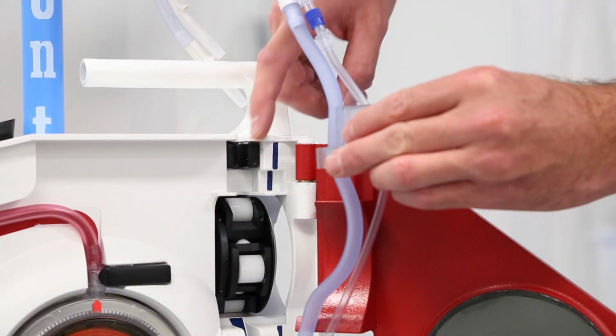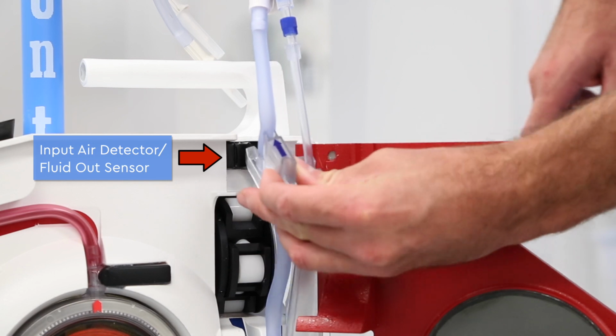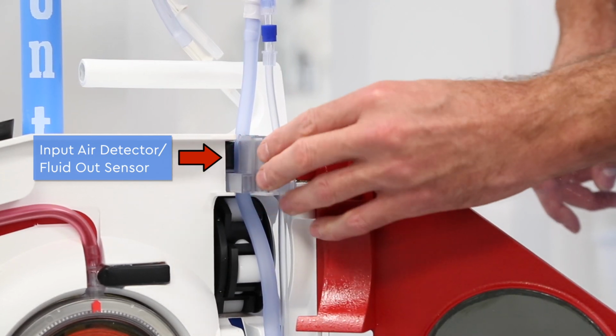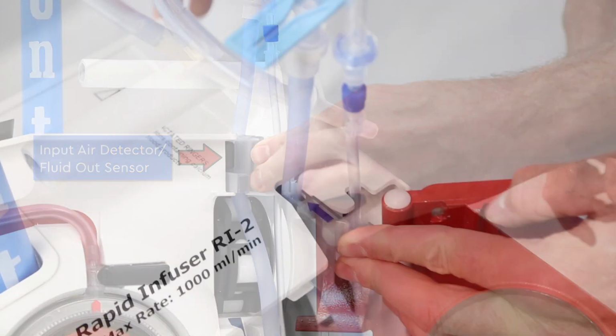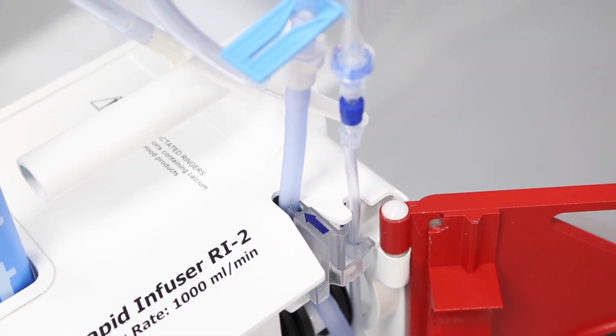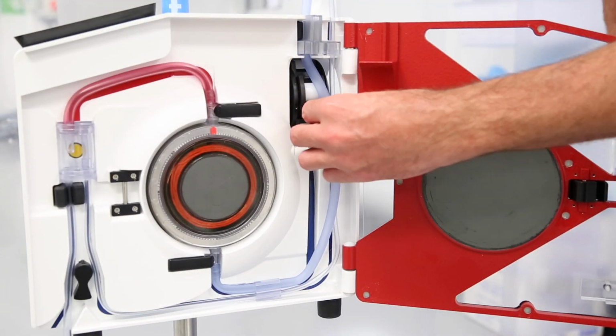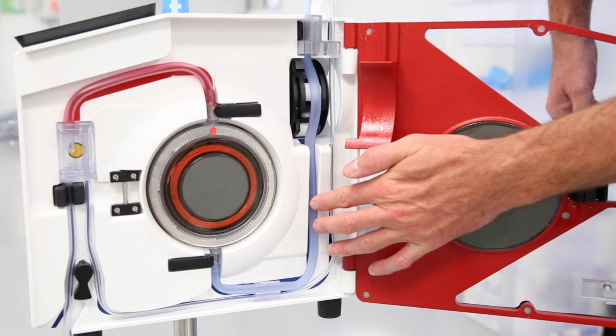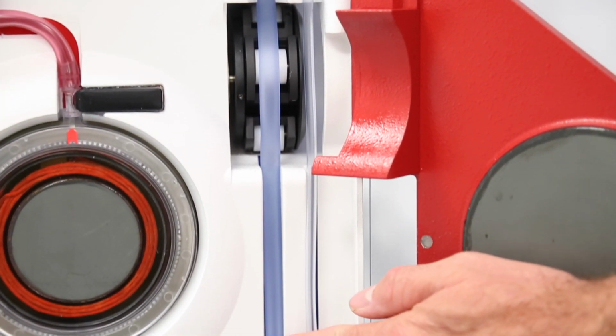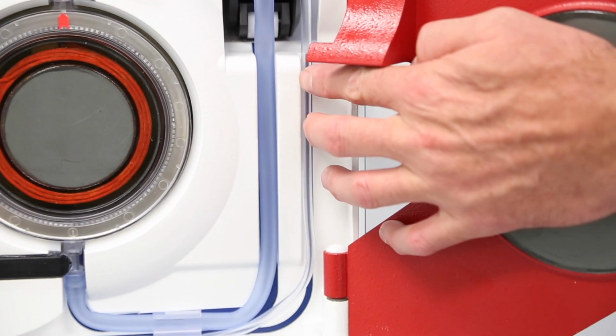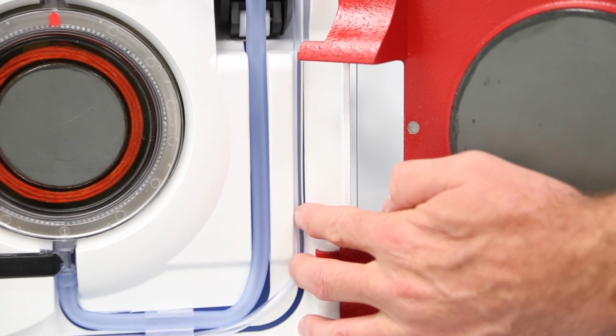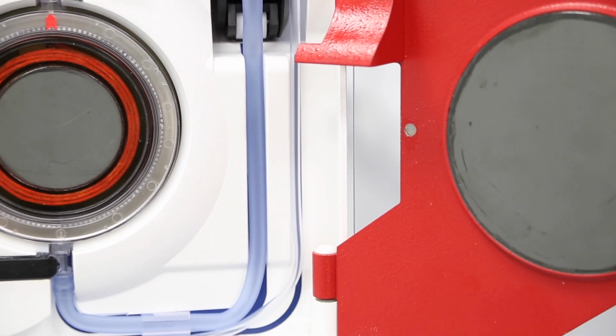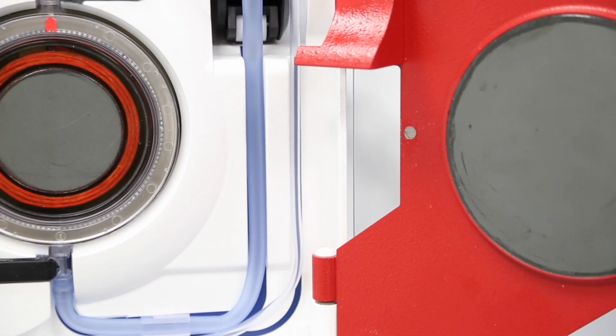Next, fit the interlock block on top of the shelf. The blue arrow should be upright, pointing towards the ultrasonic air detector. The interlock block will be flush with the top of the machine. Thread the wider tubing over the center of the roller heads. Make sure that the larger tubing is in the groove of the wider blue line and the smaller tubing is in the groove of the thinner blue line. Avoid stretching, kinking, and cross-threading the tubing.